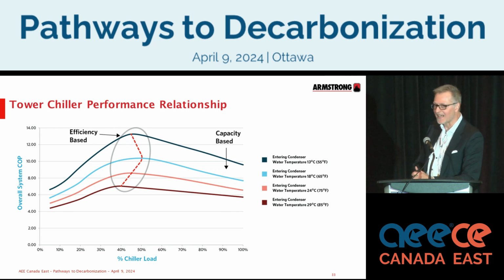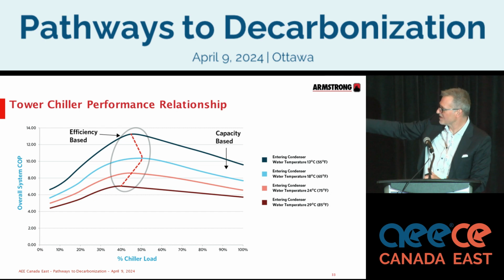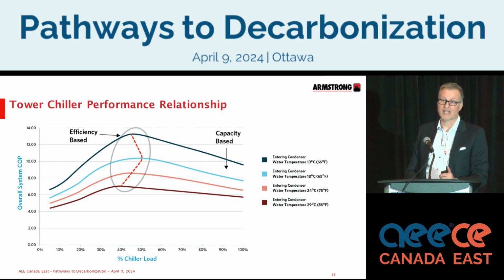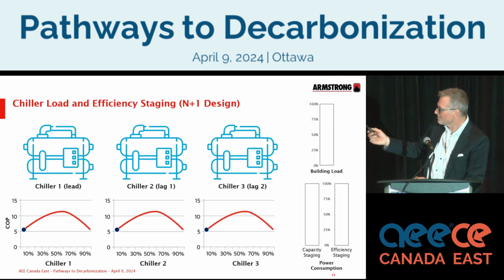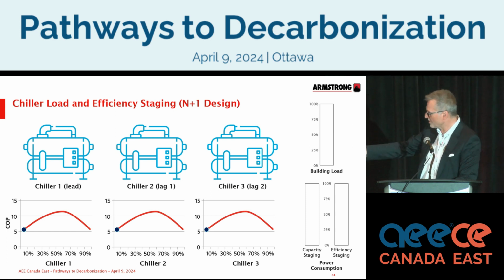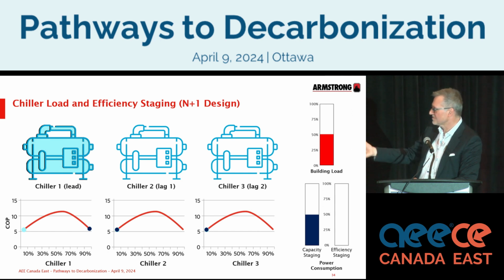The point being is that now we are mapping the relationship between the tower's performance, or the entering condenser water temperature, and the chiller's performance, and a natural curve or best staging point starts to develop with that data set. And so now, based on ambient, load, and chiller, we know where best to stage them in part load and how to split that load up. Here is a graphic that highlights this. If you're looking at traditional capacity-based staging, or sequencing, you've got a lead, a lag and a second lag chiller. First chiller, if we're looking at capacity, we're at 50% of building load. We're going to take that first chiller to 100%.